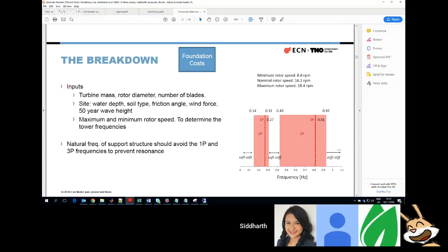Now, if you design your support structure to be in the stiff range, that means the mass of your support structure will be quite high, because it has to be really stiff and rigid, and the bending stiffness should be really high. This would have the negative effect of your support structure being really heavy, and therefore increasing costs. So generally, what foundation designers do is look at the soft-stiff range and design the natural frequency of their foundation within this range.